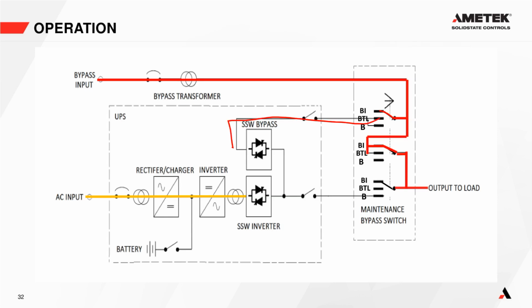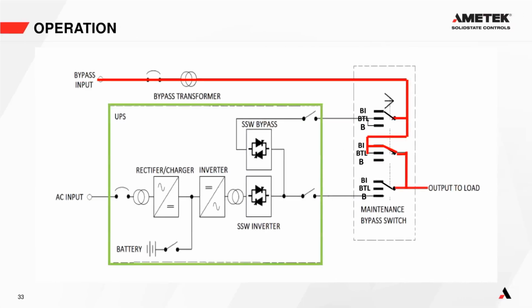Because we're now going to this contact here, and that is not allowing power flow back into here. So basically, when we say bypass isolate, what we mean is we're isolating the bypass from the bypass input to the UPS, okay? And there's a very good reason for that. And what that allows us to do is, when we're in the bypass isolate position, there is no power here.